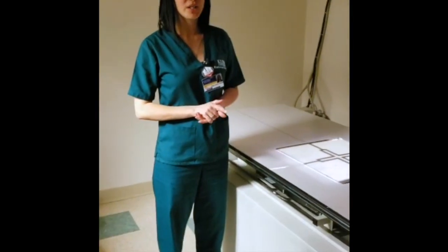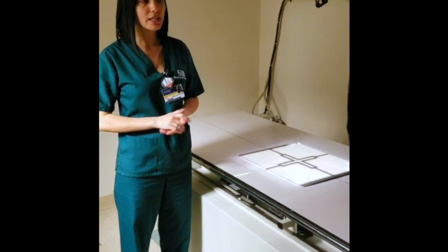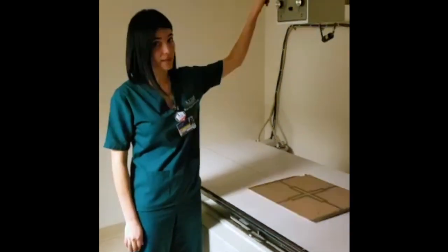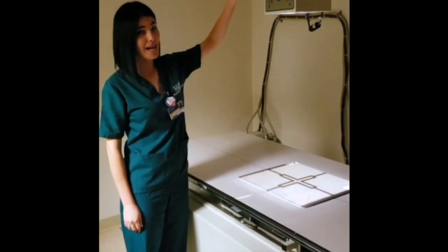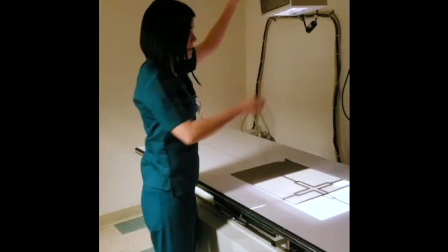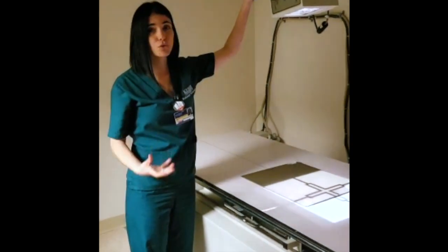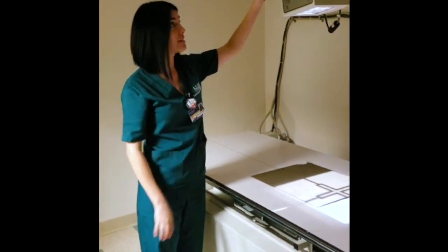The fourth error I'm going to explain is the off-level error. This happens when the angulation of the X-ray tube is not set up correctly. We have a button here that says angle. If we angle it to the side, that will produce elongation. So in our image, let's say we're doing a skull, the chin is going to look elongated. That's off level.